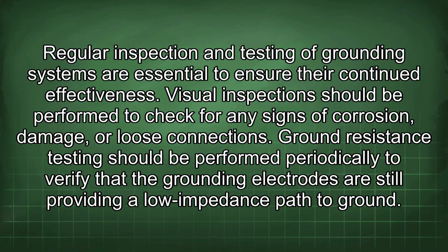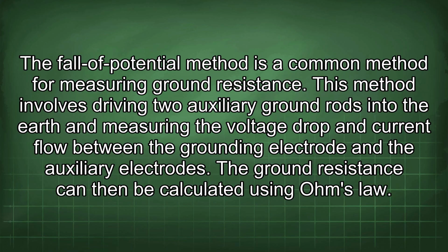Ground resistance testing should be performed periodically to verify that the grounding electrodes are still providing a low impedance path to ground. The fall of potential method is a common method for measuring ground resistance. This method involves driving two auxiliary ground rods into the earth and measuring the voltage drop and current flow between the grounding electrode and the auxiliary electrodes. The ground resistance can then be calculated using Ohm's law.